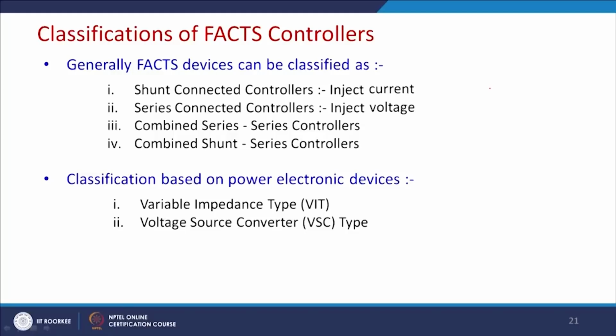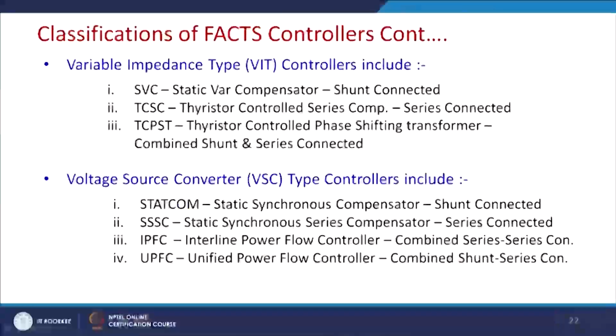So, classification can be done based on whether we are inserting impedance or a voltage source into the system. These are a few nomenclature which will be frequently used in our subsequent discussions. Students are required to note down and become familiar with these acronyms. This is basically the variable impedance type controller. It inserts impedance. SVC is a static VAR compensator, and it is a shunt connected device. TCSC, which we have seen a few slides before, is thyristor controlled series compensation, an active capacitor, and it is a series connected device.